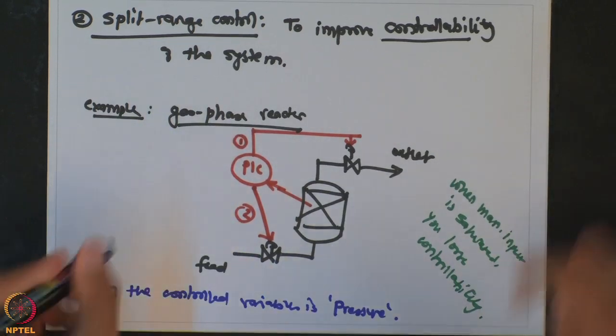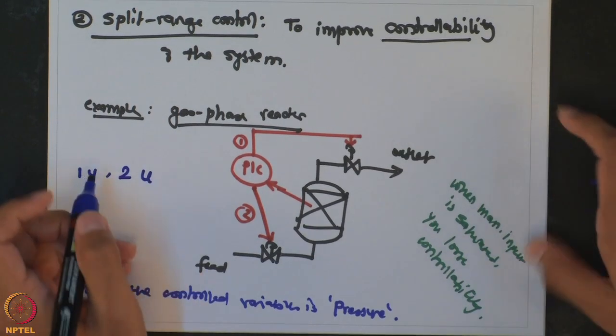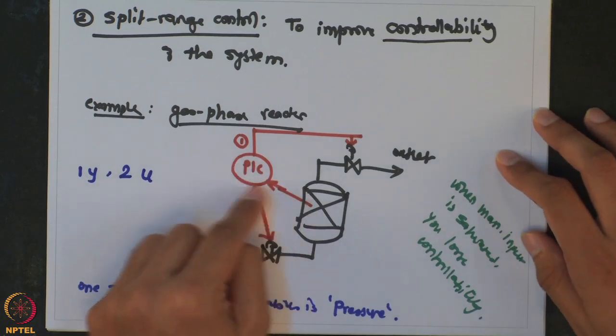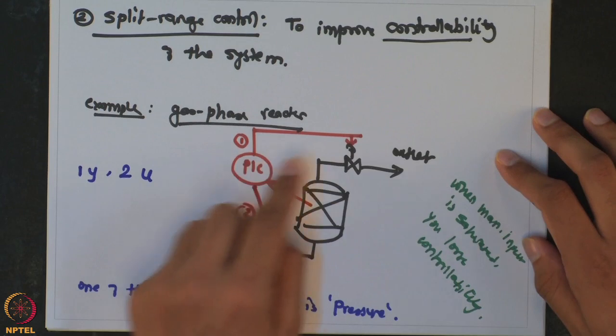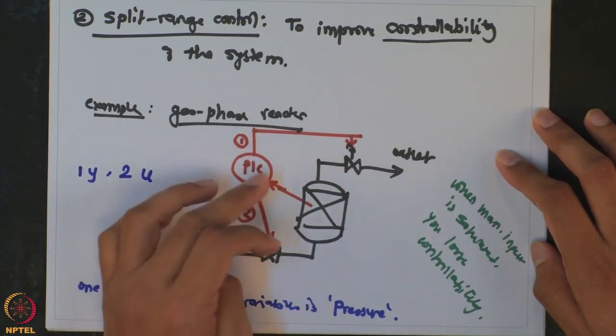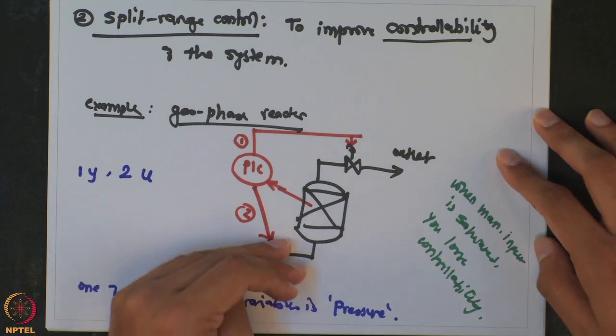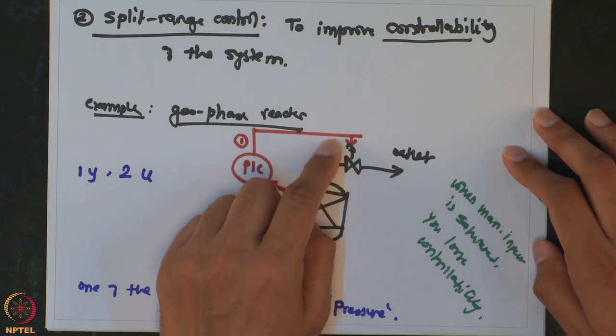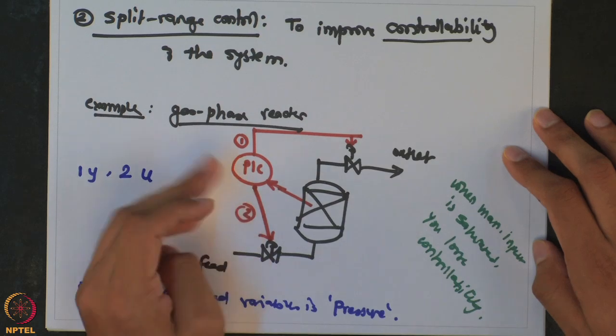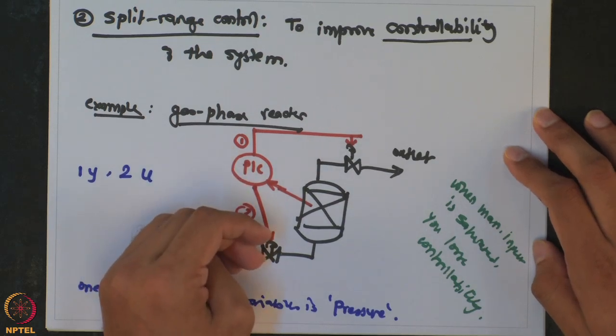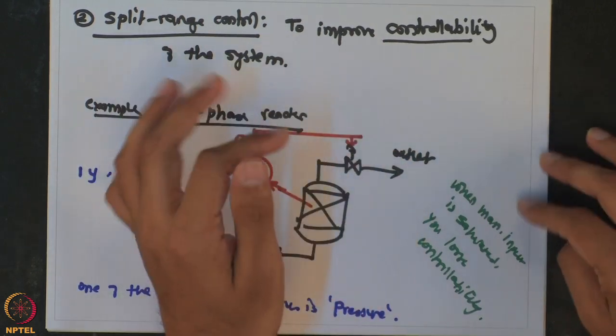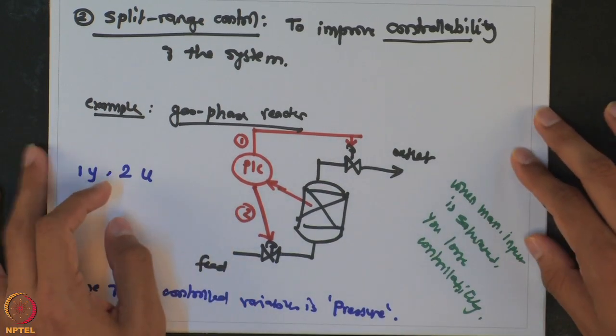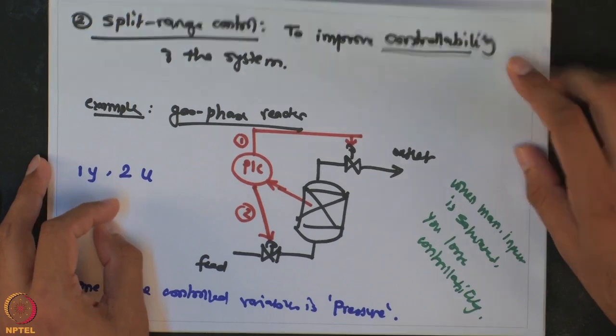What we are doing here is controlling a single controlled variable — pressure — using two manipulated inputs. They are not simultaneously active. Initially, you want pressure controlled by the outlet valve; you do not want pressure controlled by changing feed throughput. Most of the time, the controller uses the outlet valve as the manipulated input. Only when it gets saturated do you bring in the other manipulated input, thereby increasing the range over which pressure can be controlled and improving performance against large unanticipated disturbances.